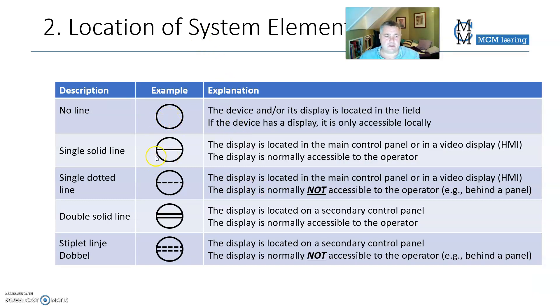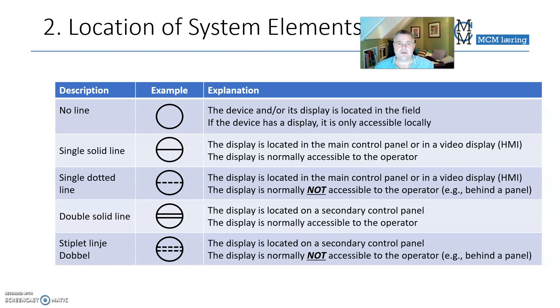The line inside the symbol describes where the system element is located. If it doesn't have a line in it, it's located in the field, so you have to go to the pipe or whatever to find the instrument and access it there. If it has a division line, it means that it's in the main control panel, so you will find it in the control room of a plant.